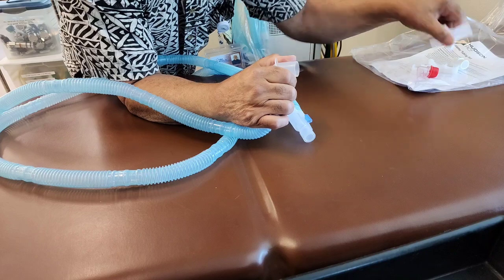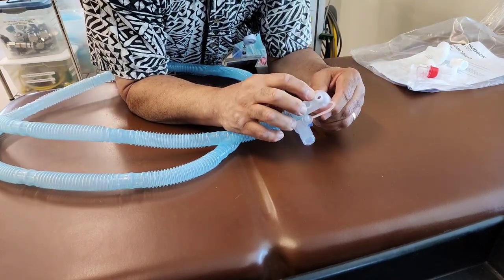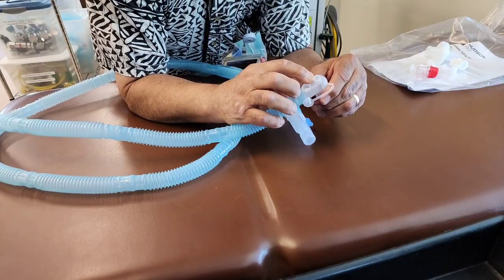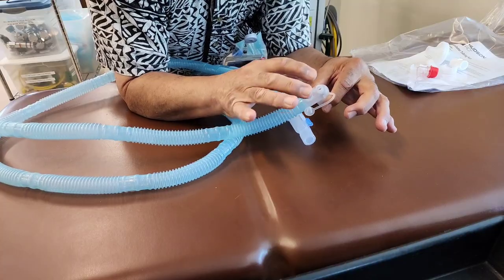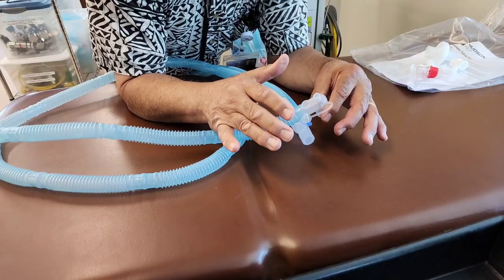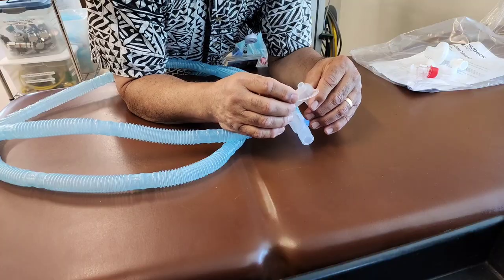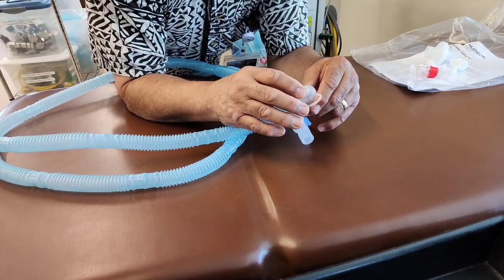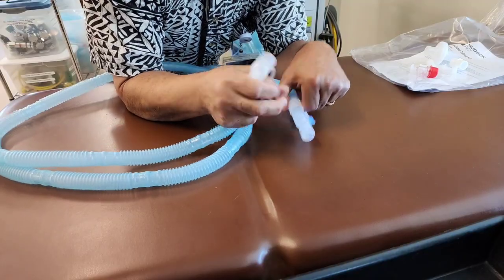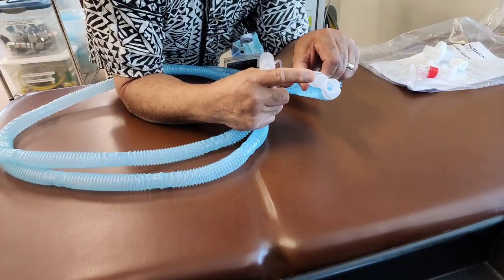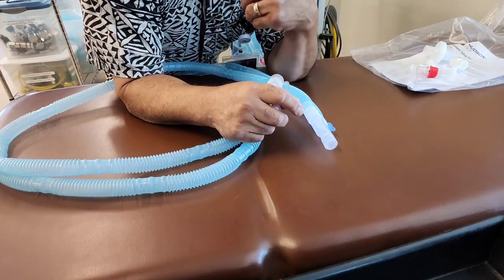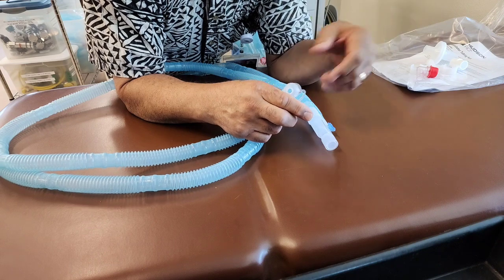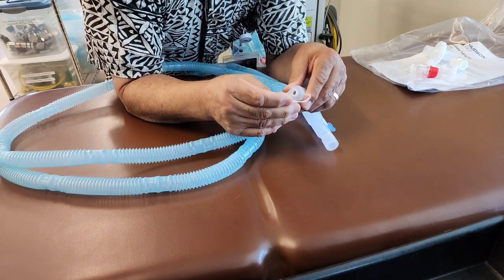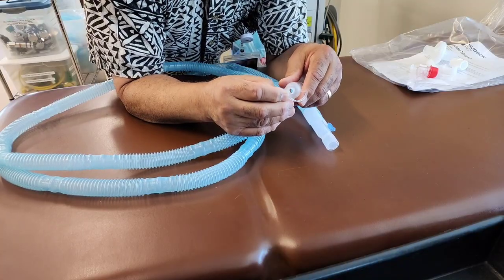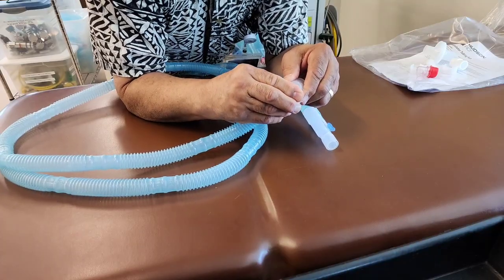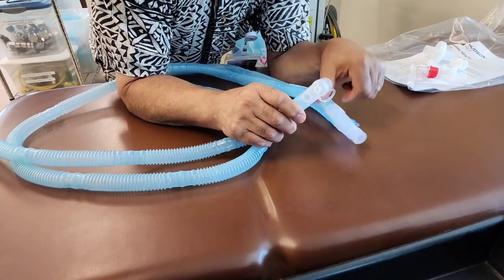Okay, I'm going to take this off for now. The other end of this has another port where you'll connect the temperature probe right here, and the probes will connect to an external heater, so you can humidify the air more effectively than a heat moisture exchanger. It's a little device that fits at the end, at the Y, where it provides some humidification for the patient. It's not 100% effective, and you'll learn about when to use HMEs and when not. But anyways, we're not going to be using HMEs in the lab, and we're not going to use external heaters. We'll just have it connected like this.